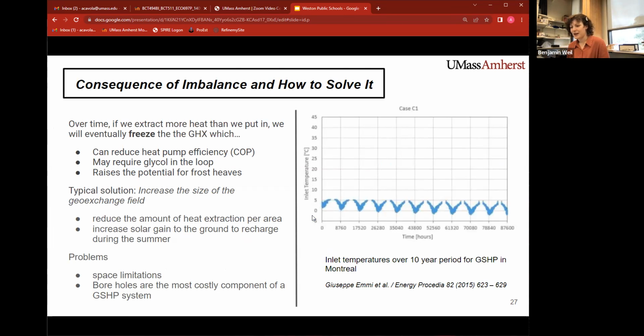So in our heating dominant climate, this is not surprising, but it does create some challenges to implementing a ground source heat pump system. Over time, if we extract more heat than we put in, we'll eventually freeze the geoexchange field, which can reduce coefficient of performance, might require adding antifreeze into the loop, which will further reduce coefficient of performance, and also raises the potential for frost heaves.